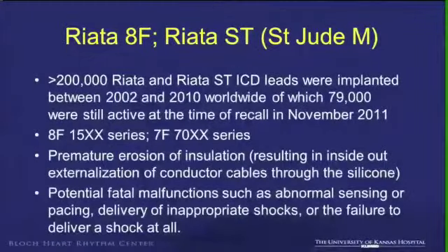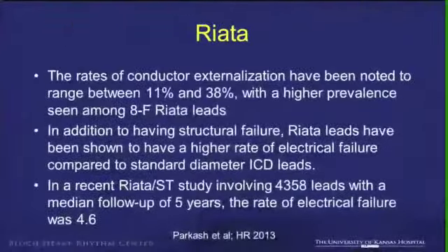So that's about Fidelis. I don't have much time, so we'll just go through the rest of the leads quickly. The RIATA leads had increasingly reported failures and an increasing frequency of fractures. About 200,000 RIATA and RIATA ST leads were implanted, and they were recalled in November of 2011. The primary problem is externalization of the conductor cables.